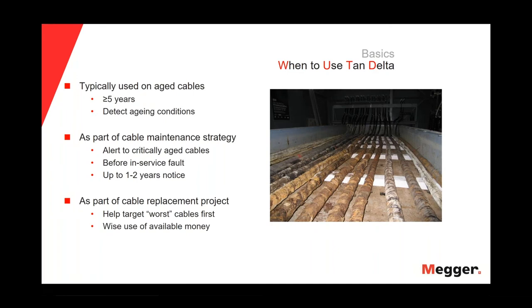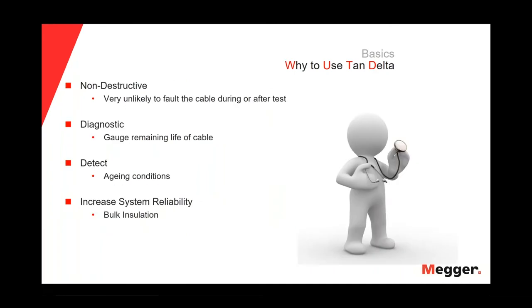So why use the tan delta? Well, first, because it's a non-destructive test. It's very unlikely for the cable to fail during or after the test. We will see later that the maximum voltage that we will apply during the tan delta test is 1.5 U0. So, again, it's very unlikely for the cable to fail during or after the test.